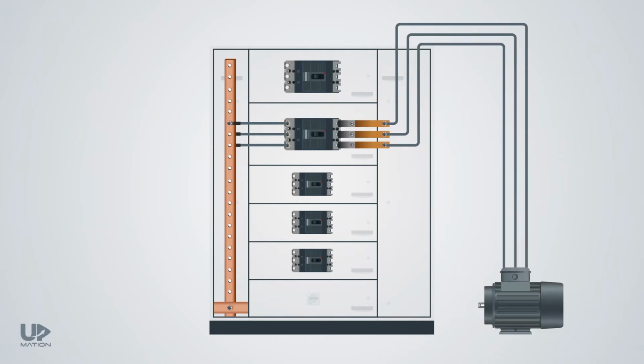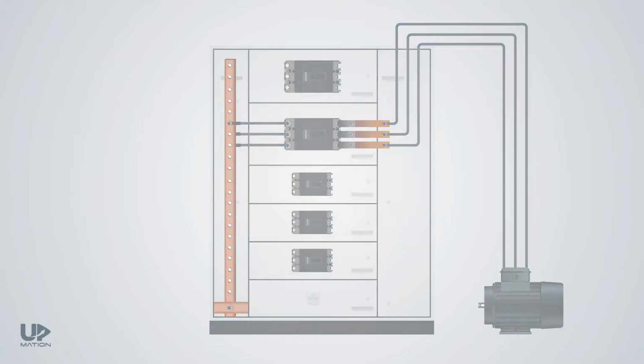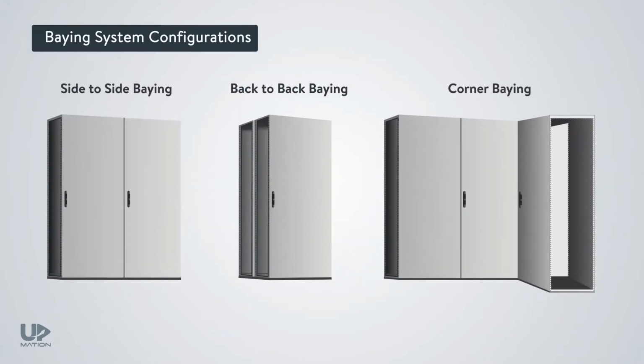This electrical MCC panel is actually a kind of side baying system in that separate panels are connected side by side. As you see here, depending on our requirements, there could be other baying system configurations as well. In these systems, as all of the enclosures are connected to each other, they have potential equalization and therefore provide more safety, and we do not have to earth each of them individually.